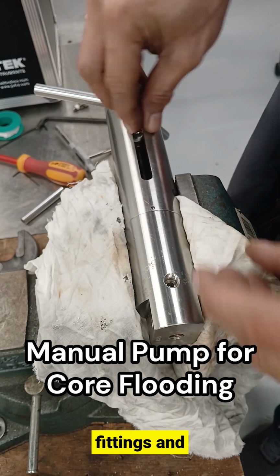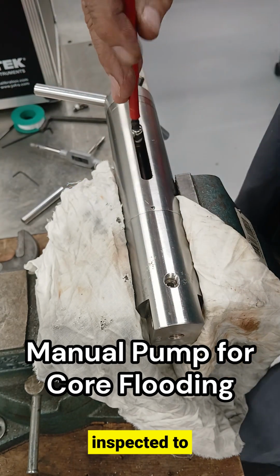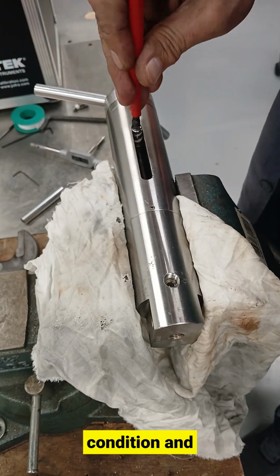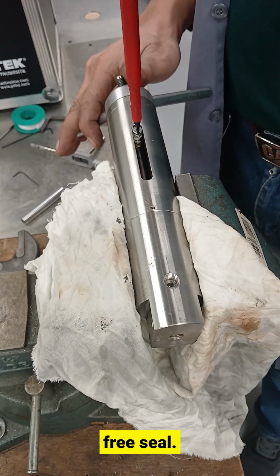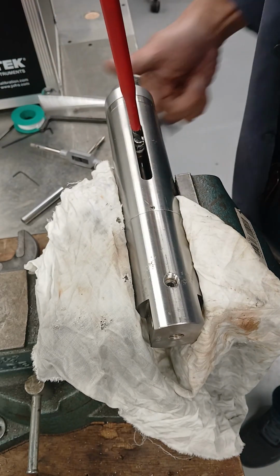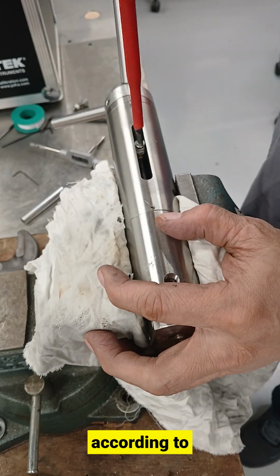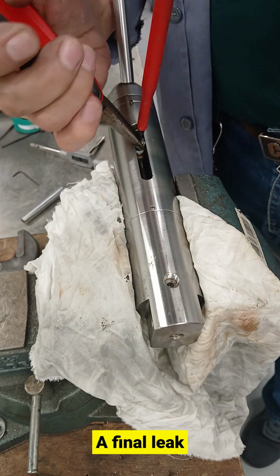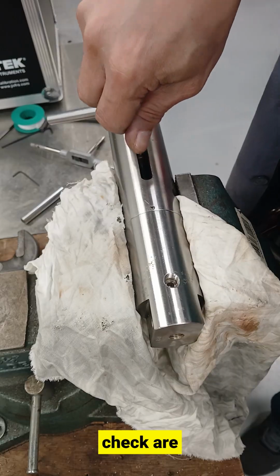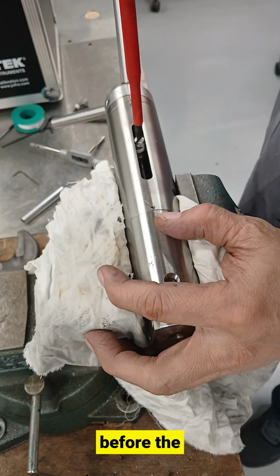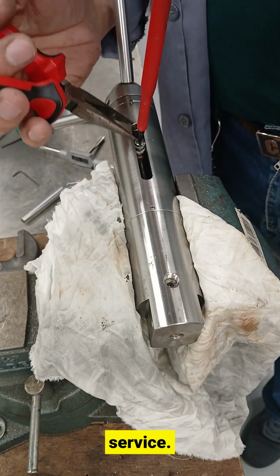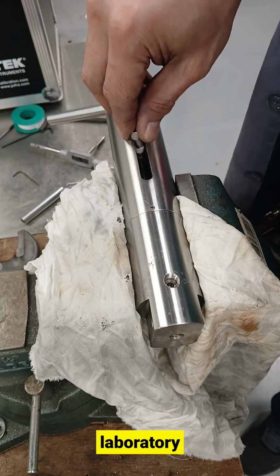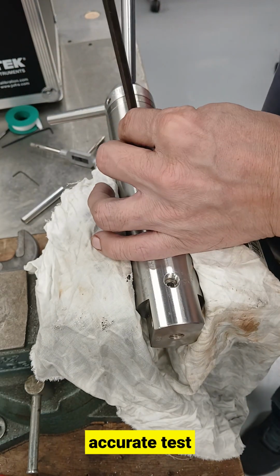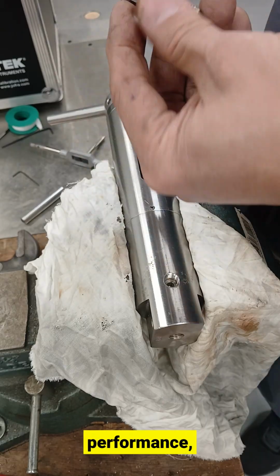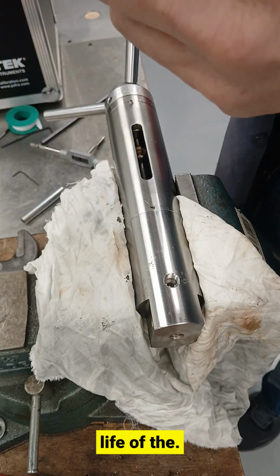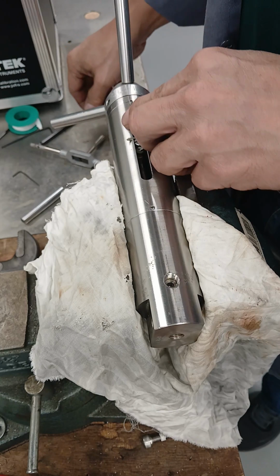O-rings, fittings, and threaded connections are also inspected to ensure they remain in good condition and provide a leak-free seal. After the inspection and cleaning process, the component is reassembled according to the manufacturer's specifications. A final leak test and functional check are performed to verify proper operation before the assembly is returned to service. Regular preventive maintenance of precision laboratory components like this helps ensure accurate test results, reliable equipment performance, and extends the service life of the entire testing system.